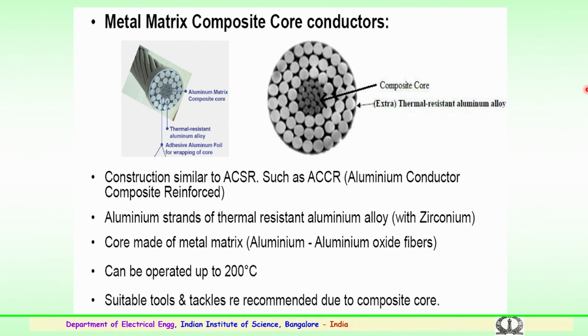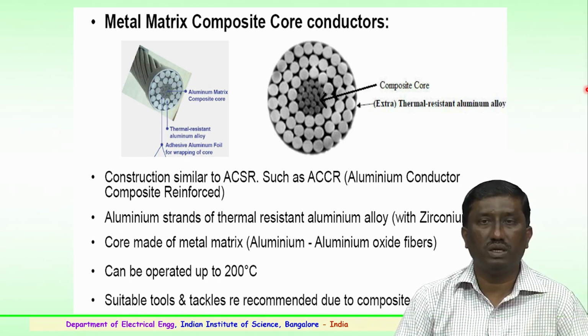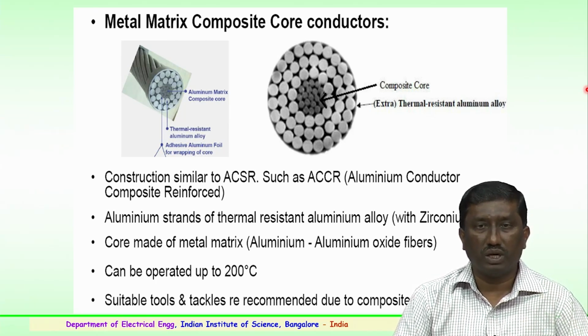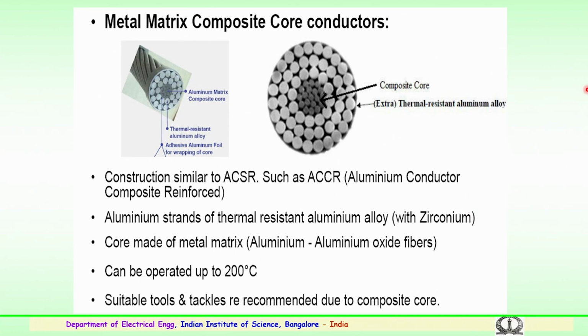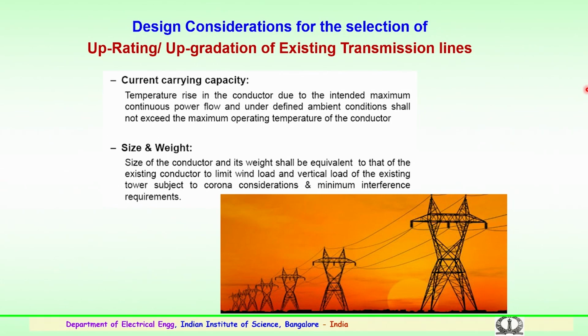Here the core is made up of a metal matrix, that is, aluminum oxide fibers. The previous one is the carbon and fiberglass core. Here the metal matrix composite core consists of aluminum oxide fibers, and this type of conductor can be operated up to 200 degrees centigrade. Suitable tools and other accessories are recommended for this type of conductor while stringing in the transmission lines. So, those were the 5 various types of recently advanced conductors which are being used for the upgradation or uprating of the existing transmission lines.